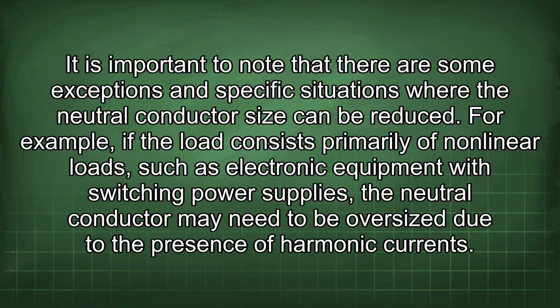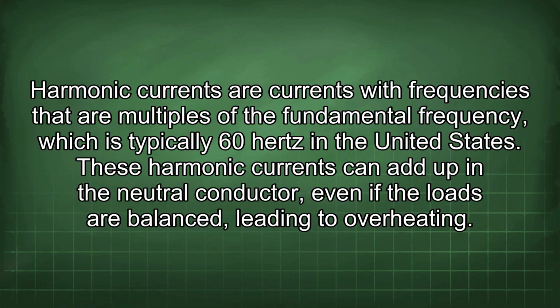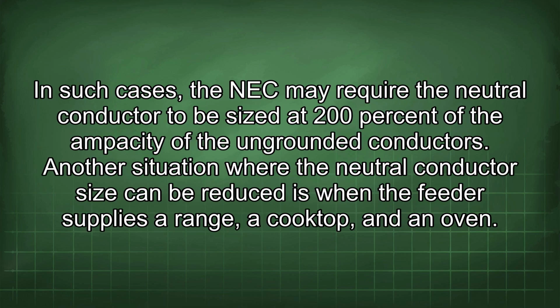It is important to note that there are some exceptions in specific situations where the neutral conductor size can be reduced. For example, if the load consists primarily of nonlinear loads such as electronic equipment with switching power supplies, the neutral conductor may need to be oversized due to the presence of harmonic currents. Harmonic currents are currents with frequencies that are multiples of the fundamental frequency, which is typically 60 Hz in the United States. These harmonic currents can add up in the neutral conductor, even if the loads are balanced, leading to overheating. In such cases, the NEC may require the neutral conductor to be sized at 200% of the ampacity of the ungrounded conductors.